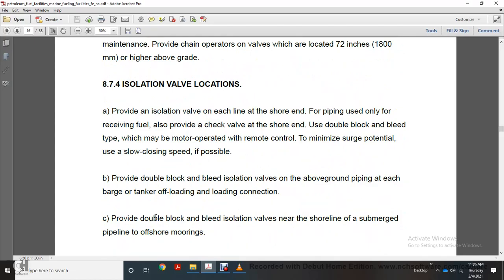Isolation valve location. Provide an isolation valve on each line at the shore end for piping used only for receiving fuel, with a check valve at the shore end. Use a double block and bleed type whenever the valve is motor operated with remote control, to minimize surge potential by using a slow closing speed. If possible, provide a double block and bleed isolation valve on the aboveground piping at each barge or tanker off-loading and loading connection.